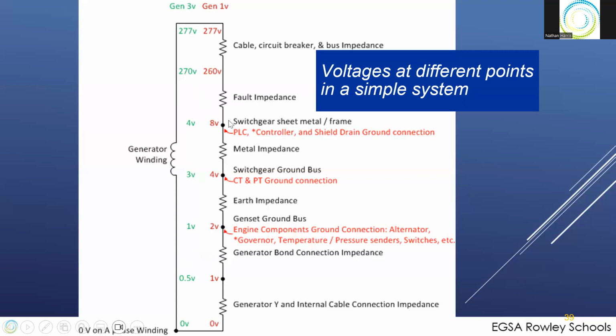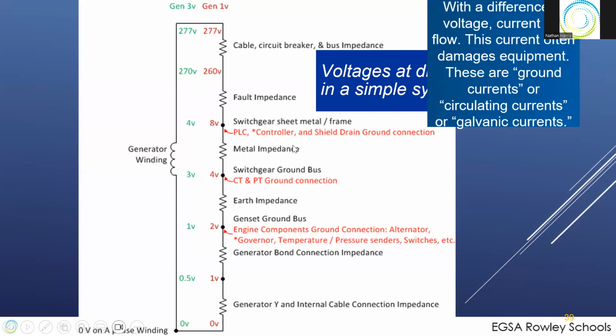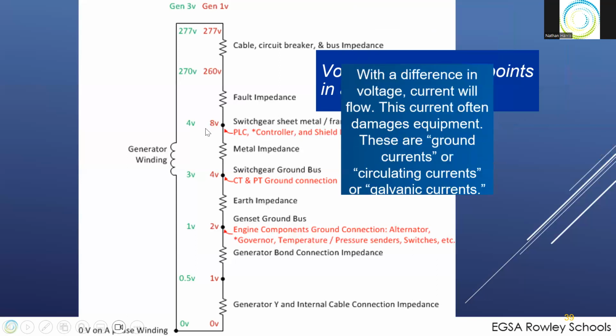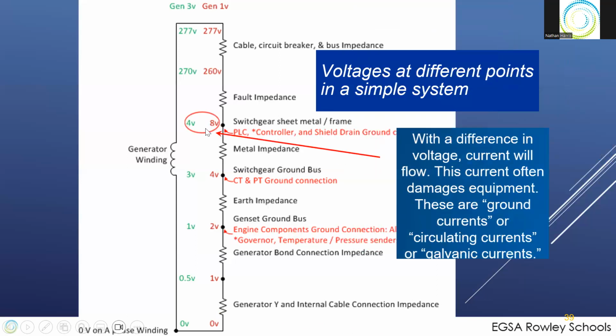And this is exactly what happened to us. We had the PLCs and the controllers here, and they're connected together with this little twisted shielded pair with a ground wire. So the ground potential between Gen 1 and Gen 3 is off by 4 volts, and that little wire is carrying lots of current from that 4 volts. And that was burning the controllers up on us.